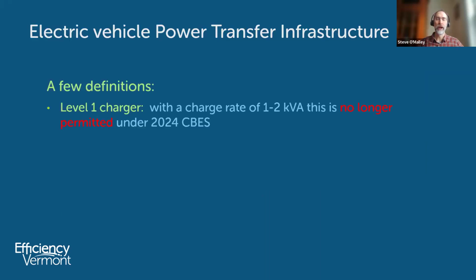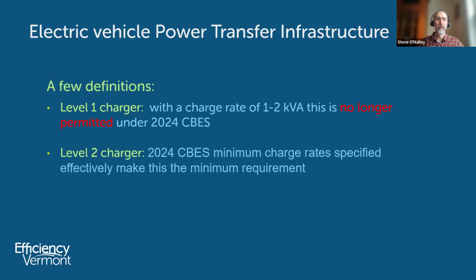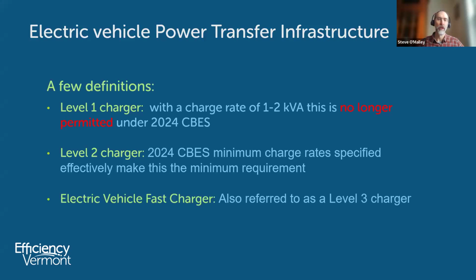Electric vehicle power transfer infrastructure. Level one chargers, which are just your 120 plug-in, are no longer permitted under the new code. Level two chargers: CBES identifies minimum charge rates specified as the minimum requirement, and level two is 3 to 8 kVA, or you can install what's called a fast charger, a level three charger.